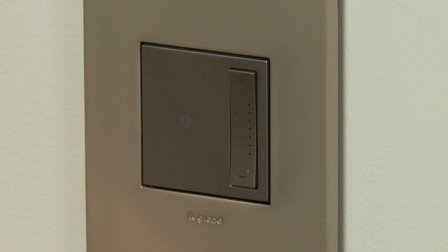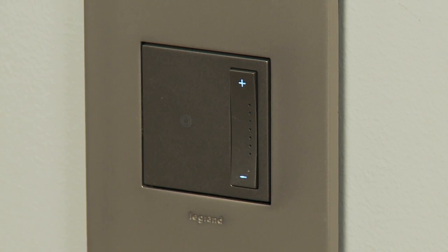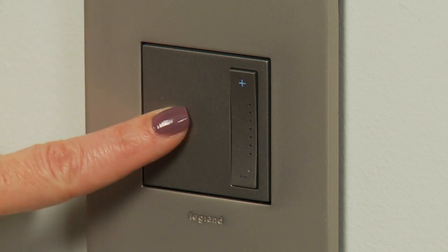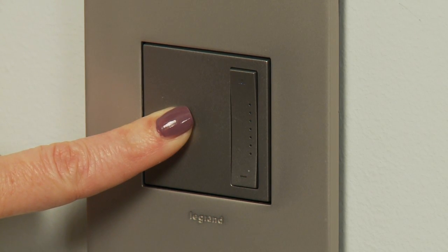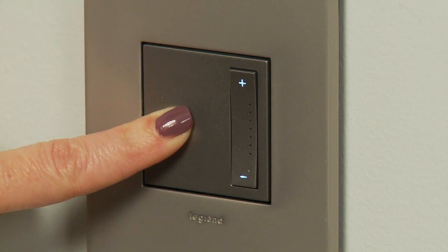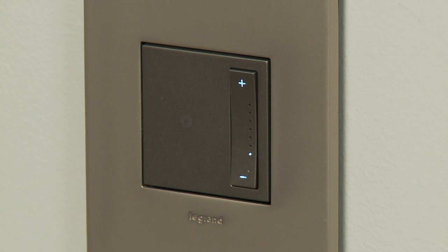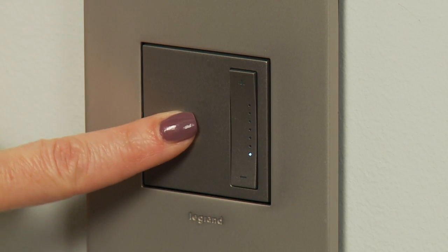To select reverse phase dimming, go back to the manual minimum trim level calibration shown in setting 1. During this calibration, simply hold the on-off button for approximately 10 seconds to toggle between forward and reverse phase. The switch from forward phase dimming to reverse phase dimming is indicated when the flash rate of the LEDs slows from 3 Hz to 1 Hz. Please note that the reverse phase setting should never be used with magnetic low voltage lighting, or damage to the dimmer may occur.